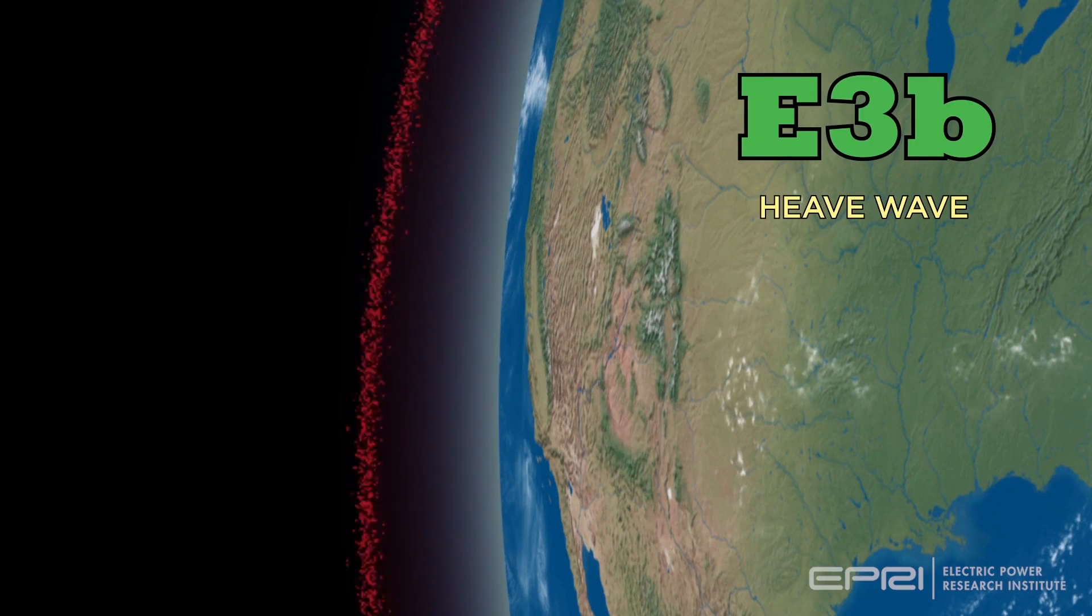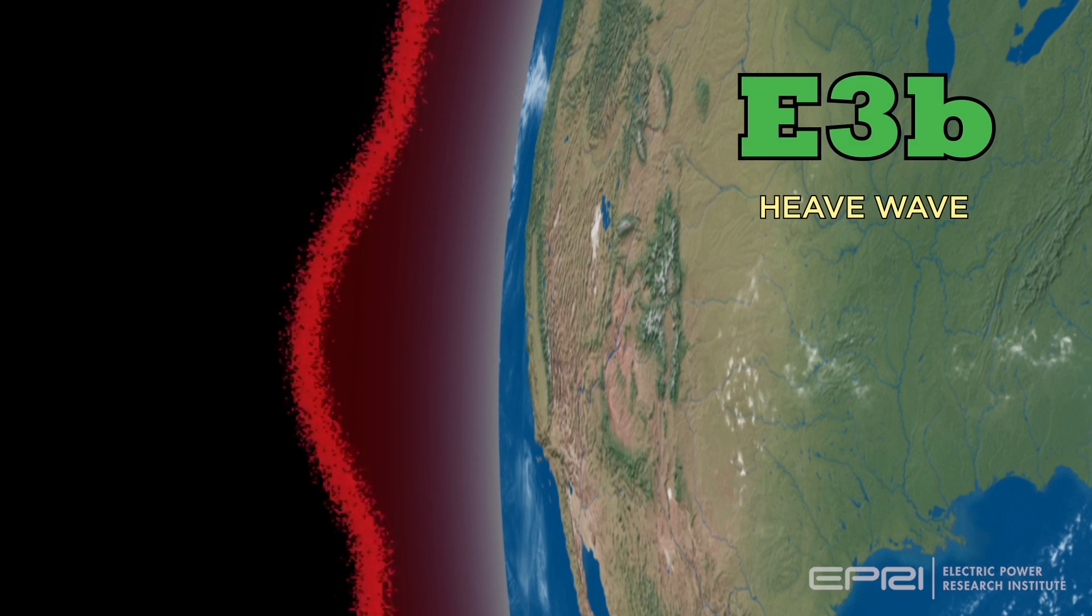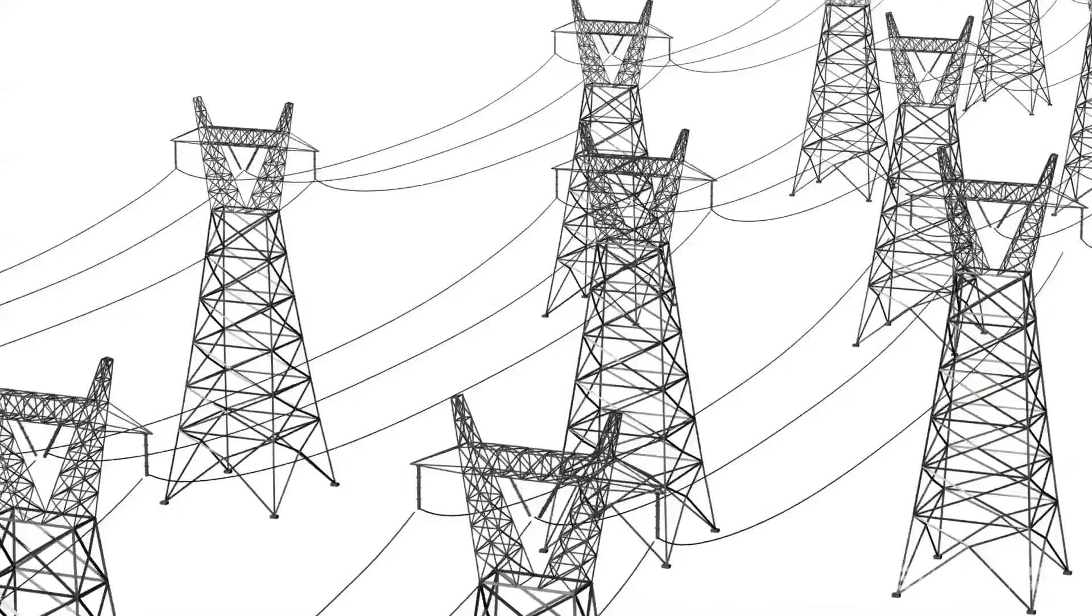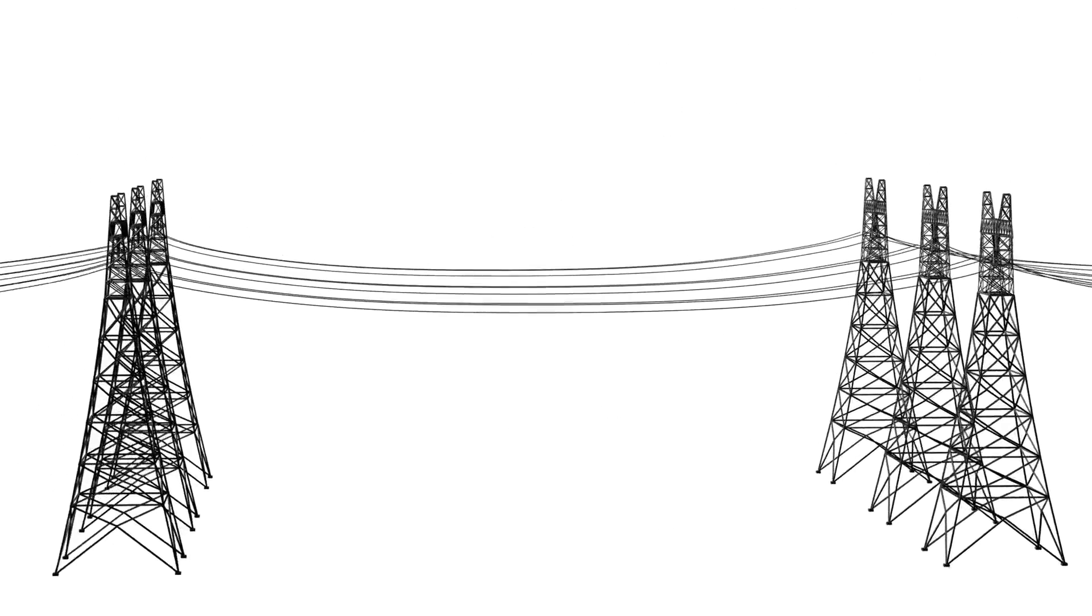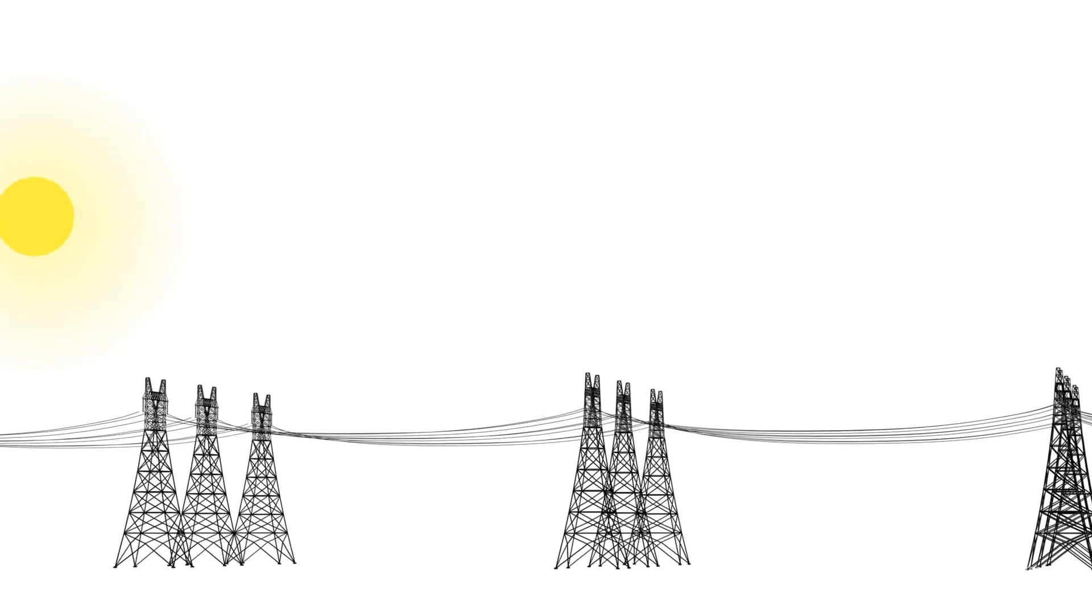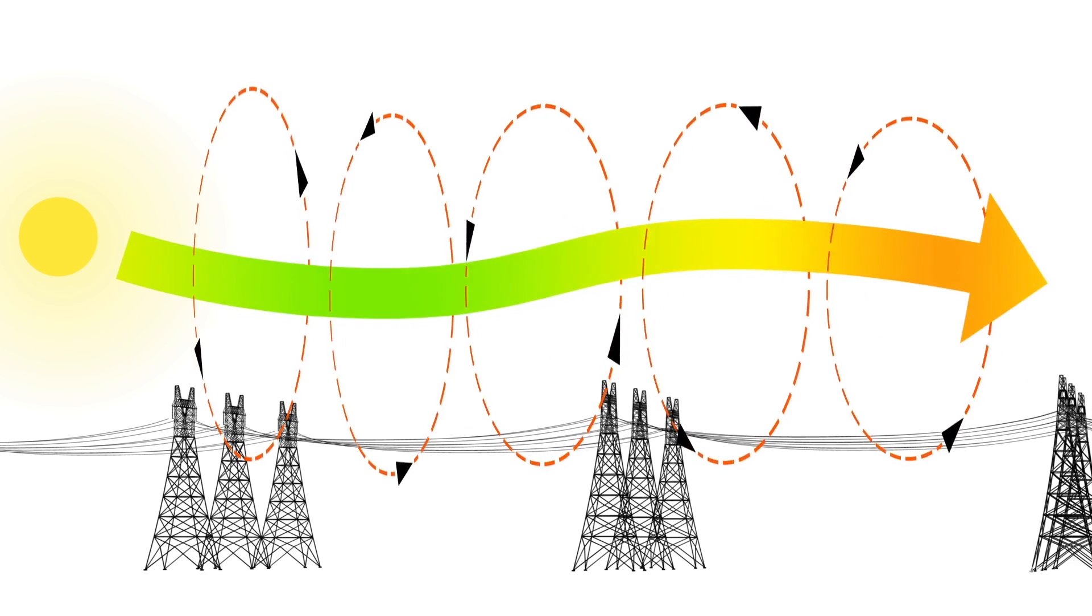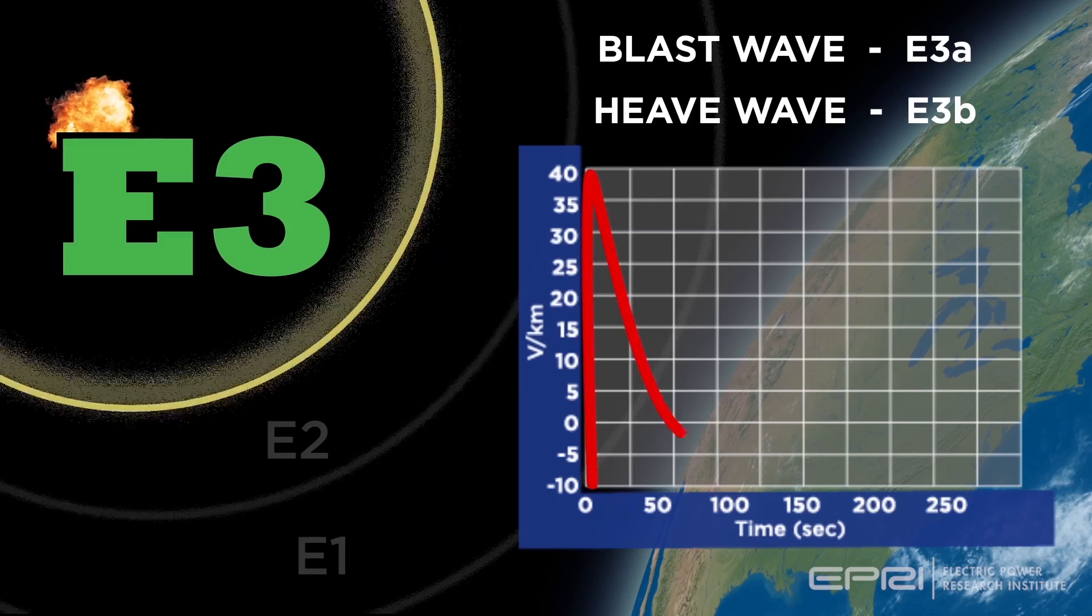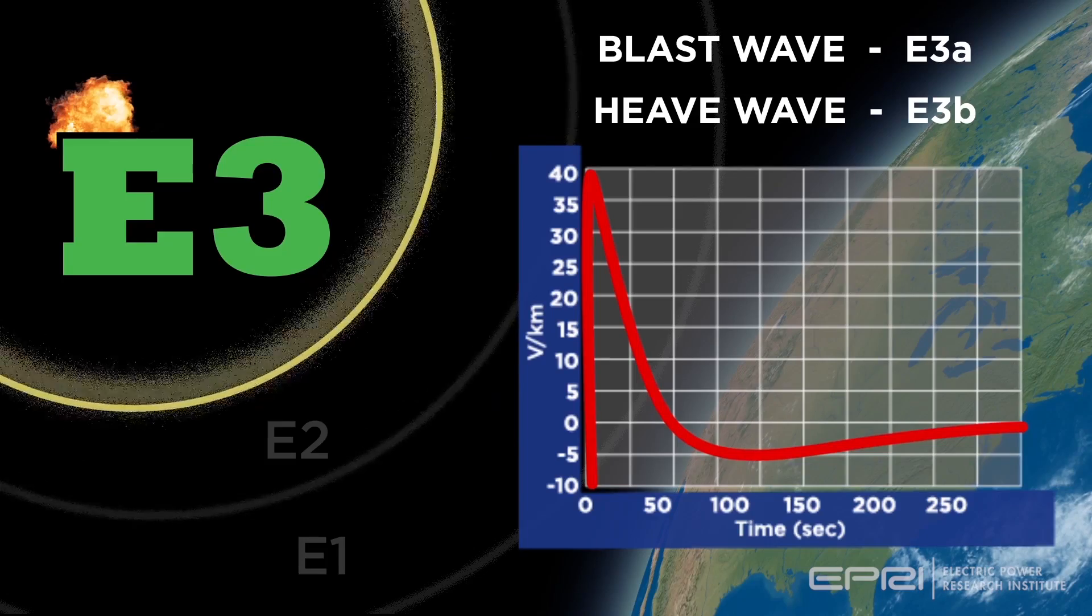The second component, the E3B heave wave, is generated by the heaving of air heated by the nuclear explosion. The change in geomagnetic field resulting from the E3A and E3B waves induces low-frequency, quasi-DC, currents in the power grid, much like those generated by a severe geomagnetic disturbance event, but are significantly larger and of much shorter duration. The total duration of the E3A and E3B signals is on the order of four to five minutes.